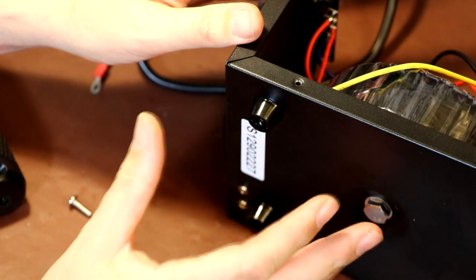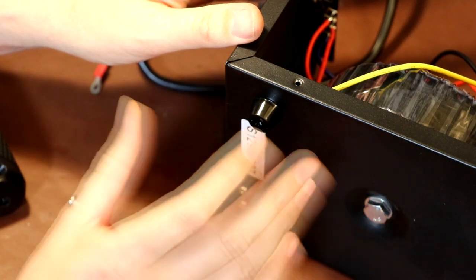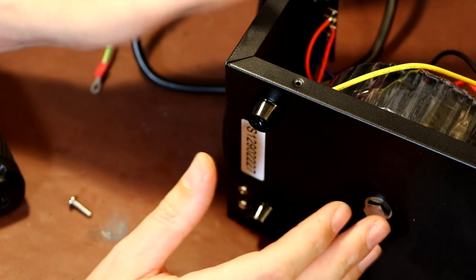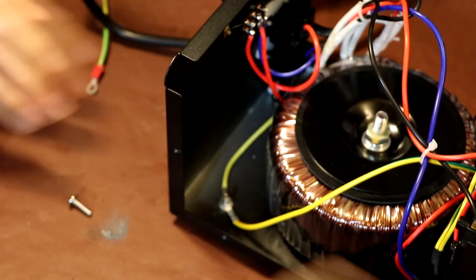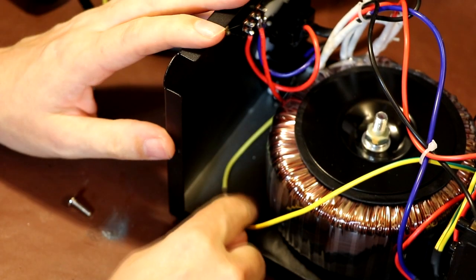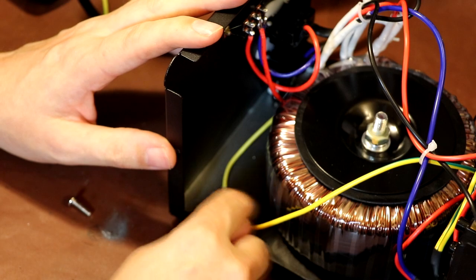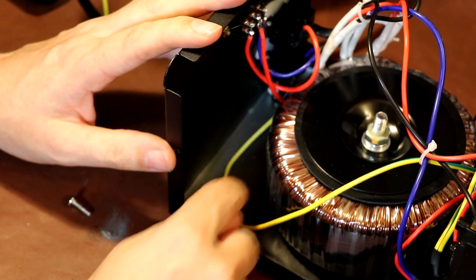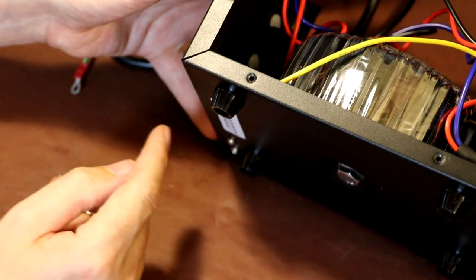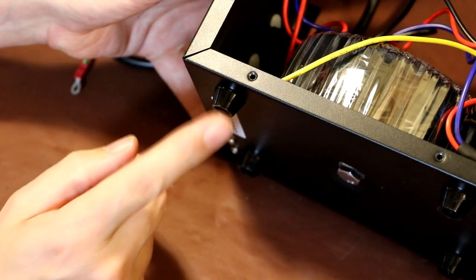So you must not use fixings for a purpose other than what they were intended for. If you want to earth the case here, you should drill a hole and use a separate earth stud. We shouldn't use one of the fixings which is being used to hold on the feet. That is wrong, so that's a fail.